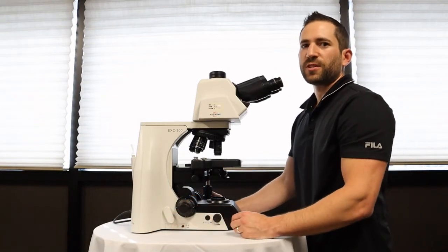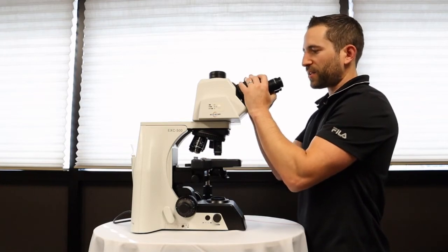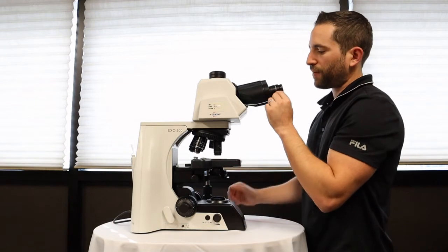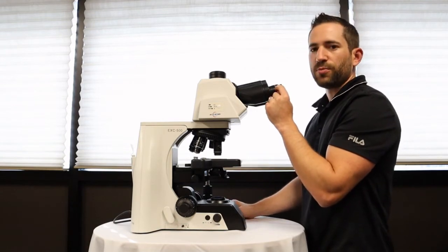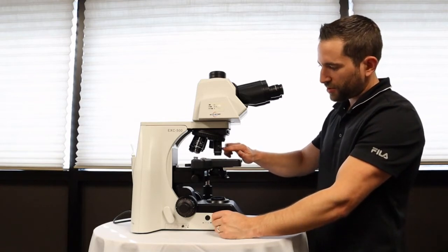A microscope for a pathologist would typically be an ergonomic microscope. That involves an ergonomic tilting head so you can adjust the eyepiece inclination. It will typically have large 20 or 22 millimeter field of view eyepieces, and a must is a 2x objective lens.